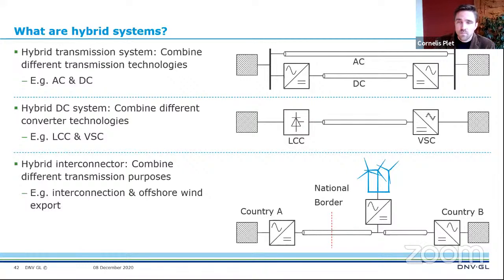The first is a hybrid transmission system, as Jochen already mentioned. It's a transmission system consisting of both AC and DC connections within the same interconnected electrical grid, and the DC links in such a grid are often called embedded HVDC links. They typically arise from regular AC grid expansions or reinforcements where, due to environmental or societal reasons, cables had to be used rather than transmission lines. If those projects exceed a certain distance, AC technology is no longer viable and DC must be used. This also brings another advantage: if you use VSC HVDC technology, the link is fully controllable and can optimize AC grid operation in terms of congestion, losses, and reactive power management, adding to grid reinforcement without increasing local fault levels.